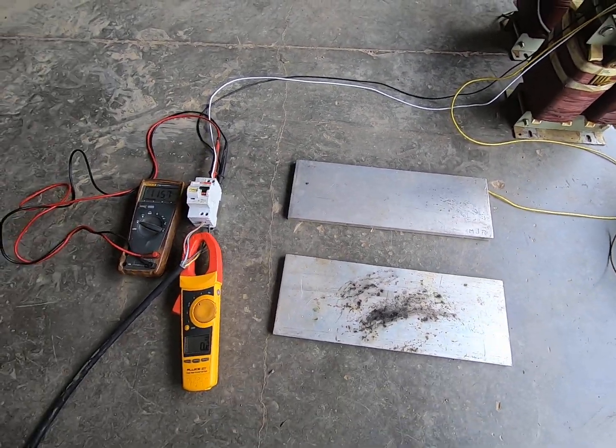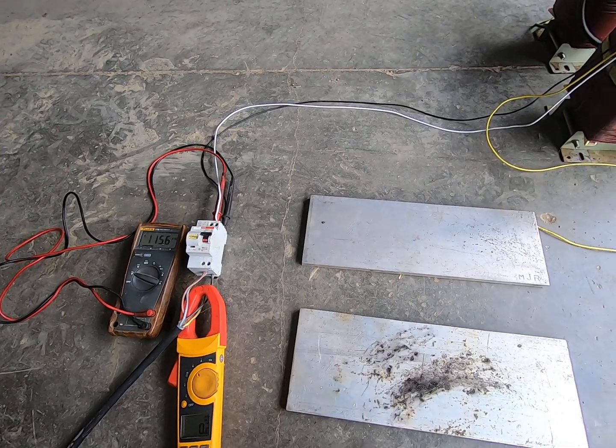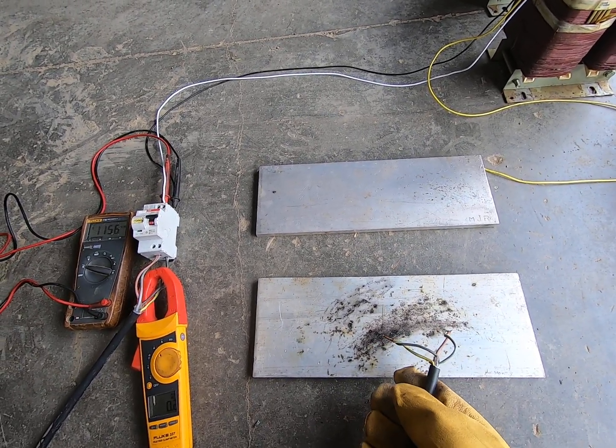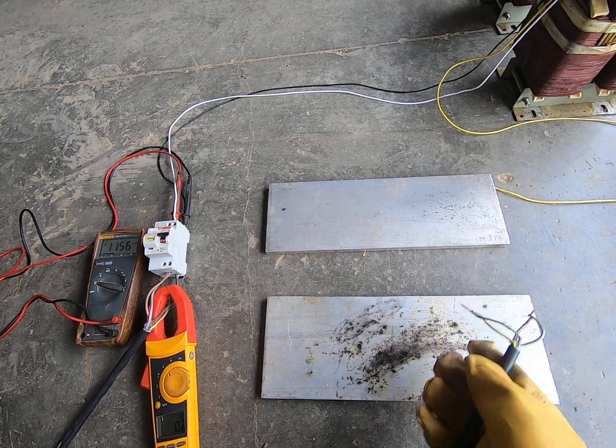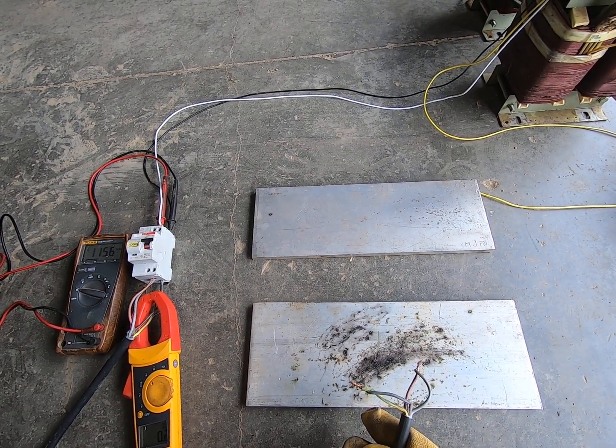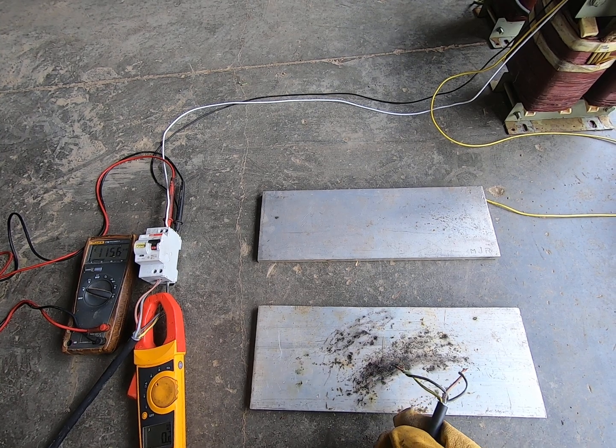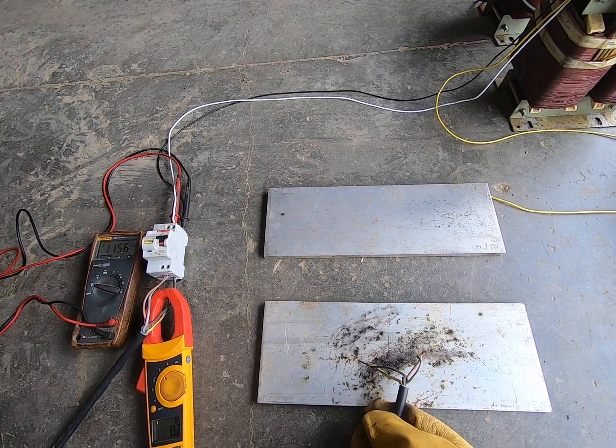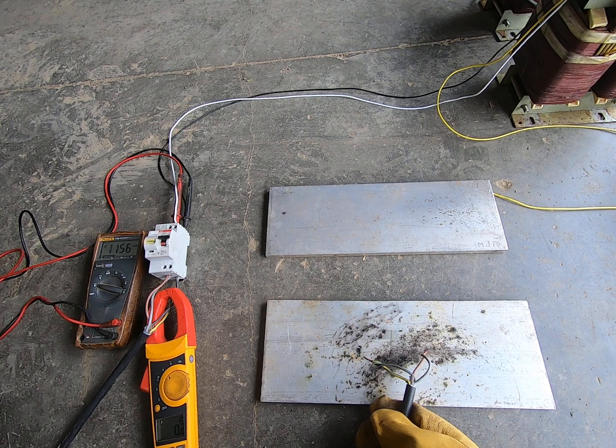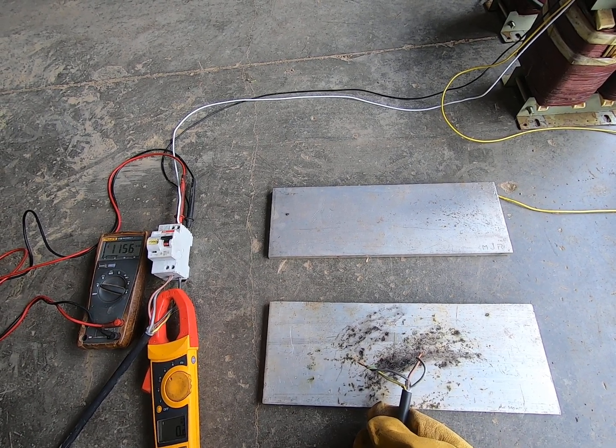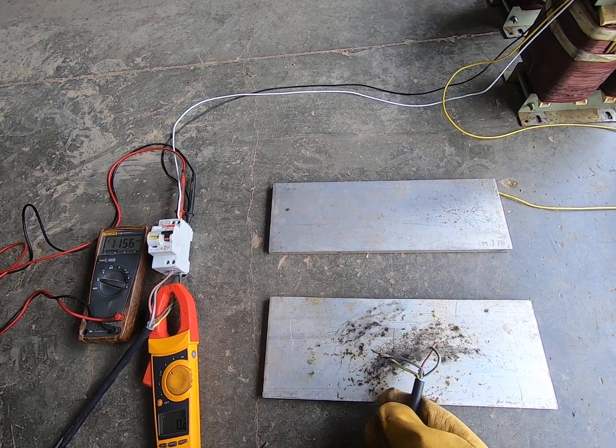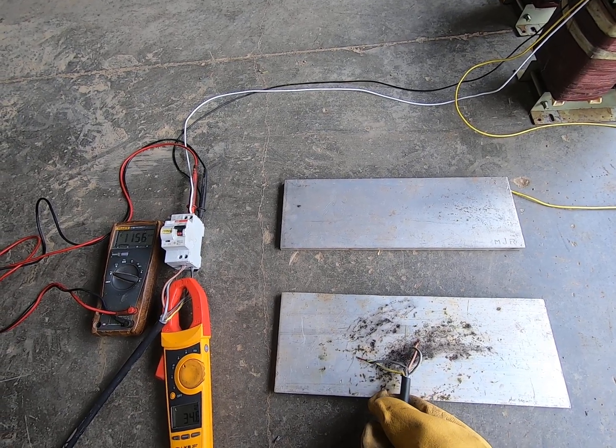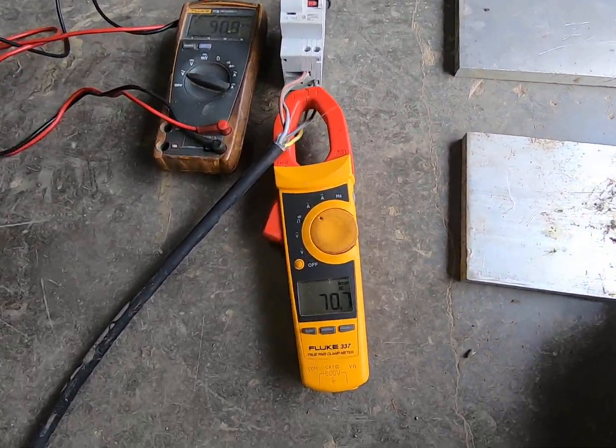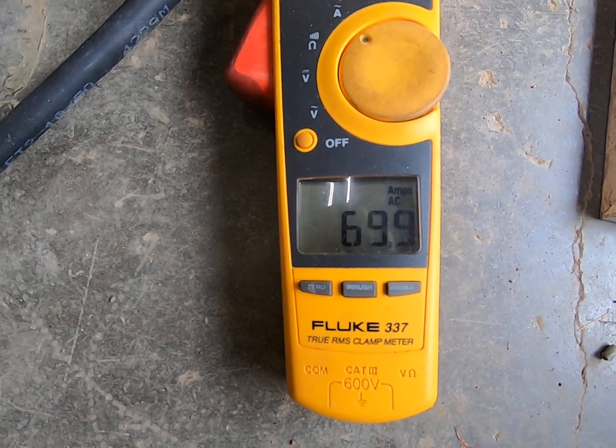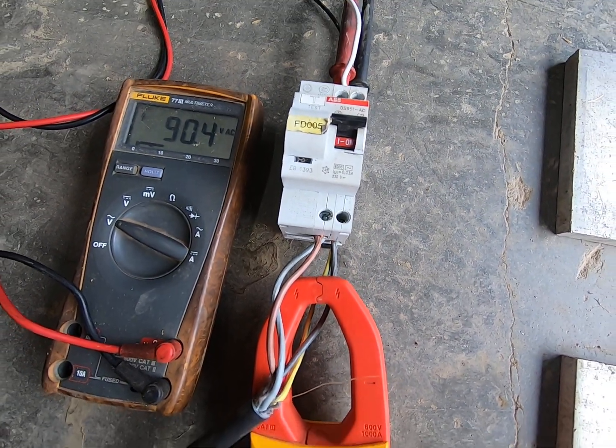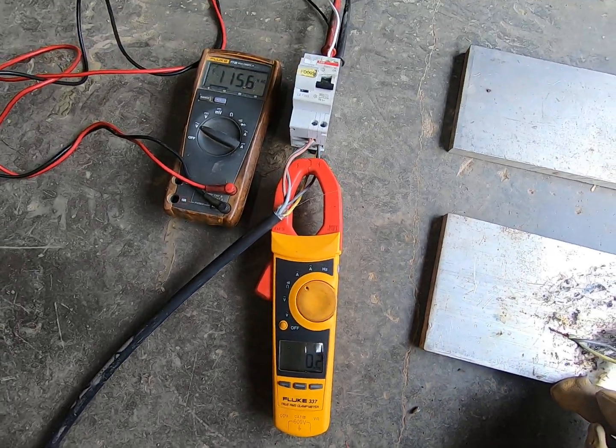Now, a third test I can do is just a straight phase-to-phase short without a ground being in the circuit. So in this case, if I were to short together phase-to-phase, so this could be the cable shorting against something metal that's not grounded, or the cable shorting against itself. What you'll notice is I'm drawing about 70 amps, and the breaker has not tripped yet. So there, the breaker tripped.